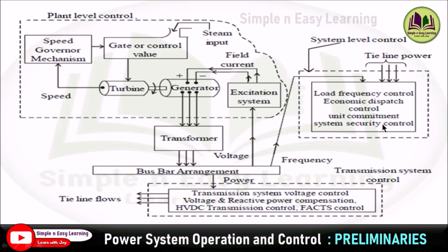The system control actions are carried out by system control centers, which must have information including control area frequency, output of generating units, and tie line power flow to interconnected areas, with separate control centers for each area. There are four levels of control actions. In the first level, control actions are carried out at the generating station and substation using a local control center with remote terminal units (RTU). In the second level, control of the sub-transmission network is carried out by the area control center. In the third level, control of the transmission system is carried out by the state load dispatch center using SCADA. In the fourth level, control of the interconnected power system is carried out by regional control centers.